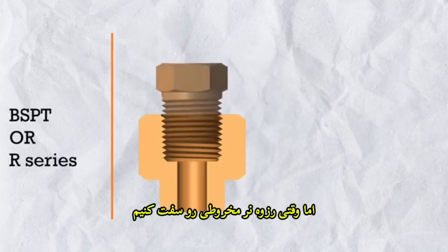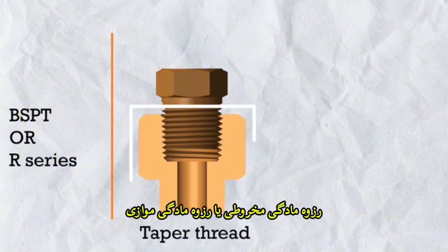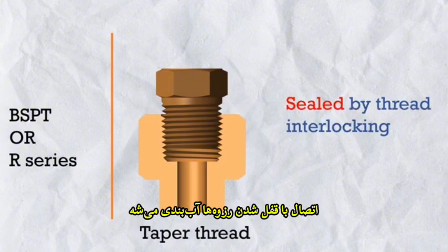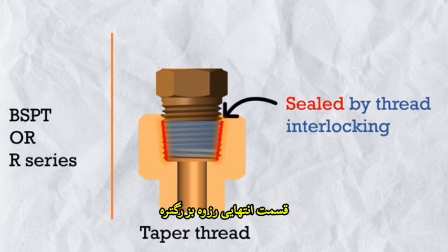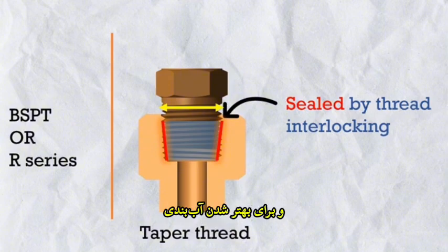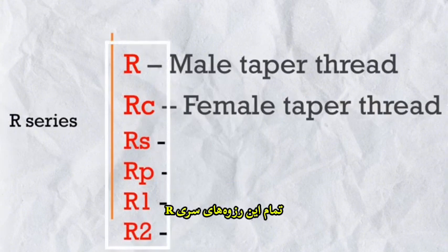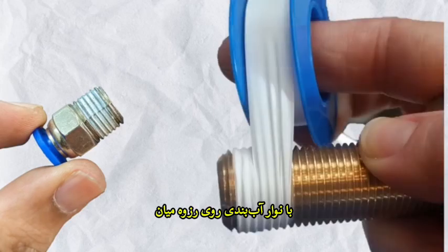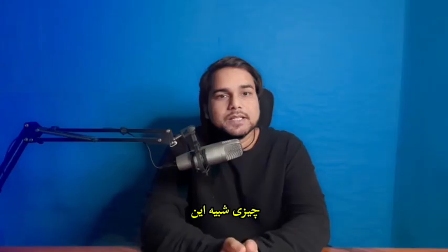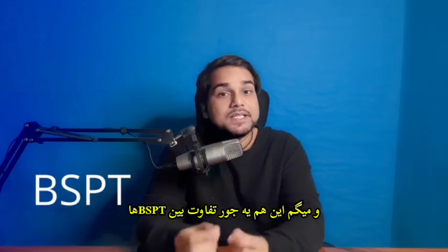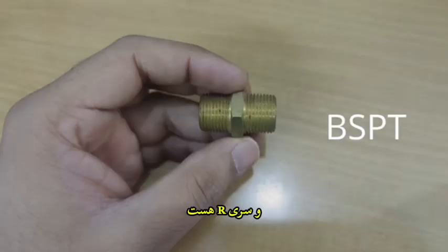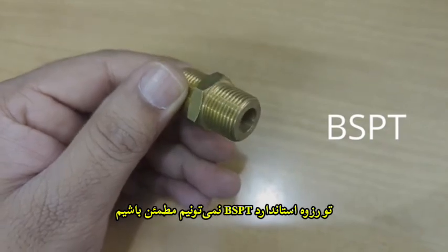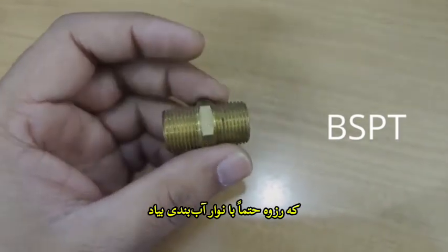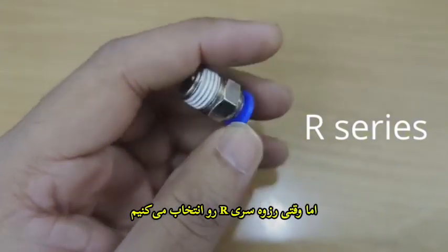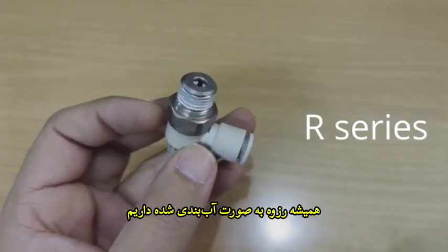But when we tighten the male taper thread, either with taper female thread or parallel female thread, the connection will get sealed by thread interlocking. Because it's taper, the end portion of the thread is larger, and to improve the sealing, all these R series threads come with sealing tape over the thread, something like this. And I would say this is also a kind of difference between BSPT thread and R series thread. In BSPT standard thread, we cannot be sure that the thread will come with sealing tape. But when we choose R series thread, we always get a sealed thread, something like this.